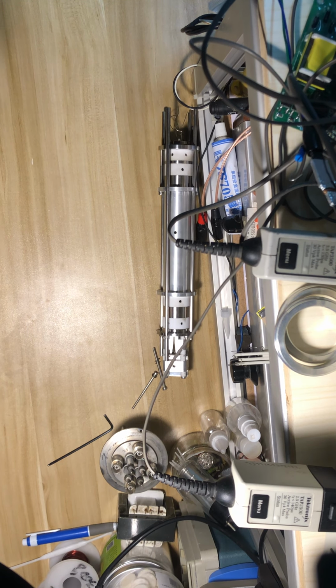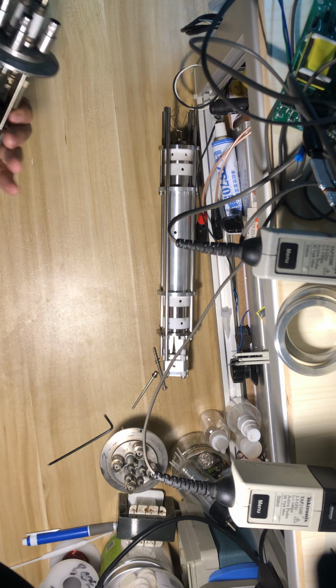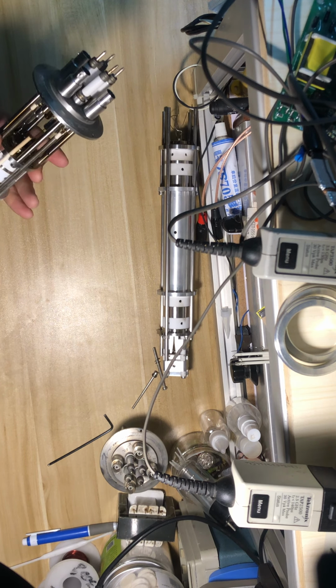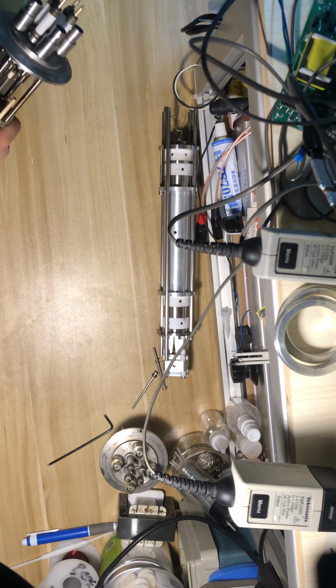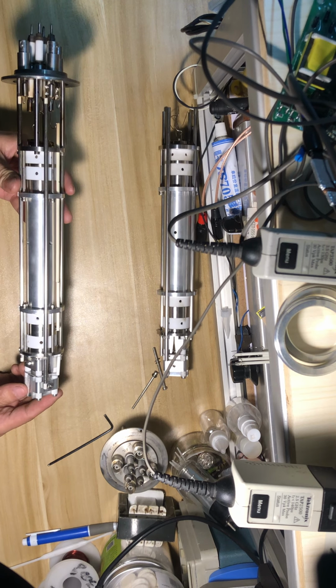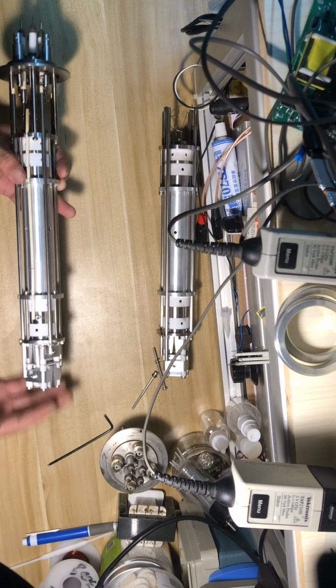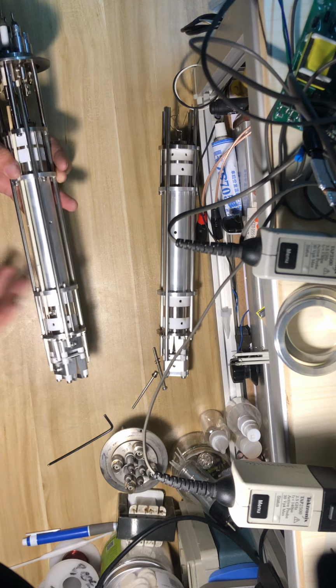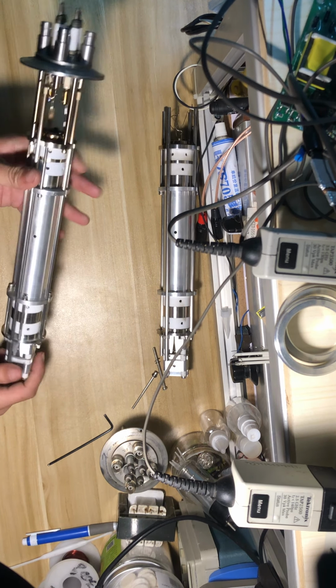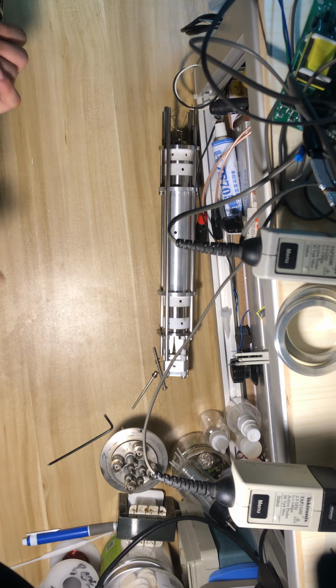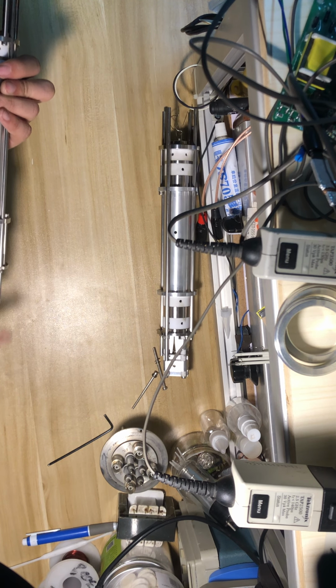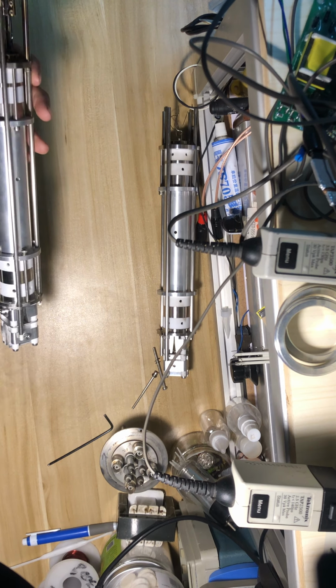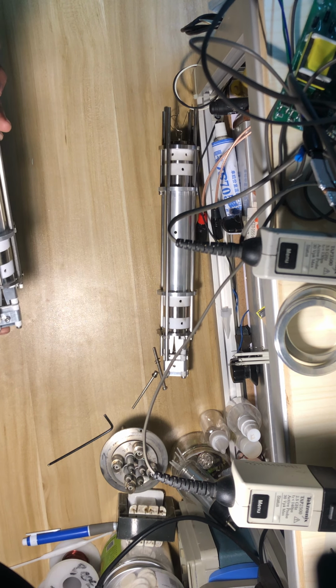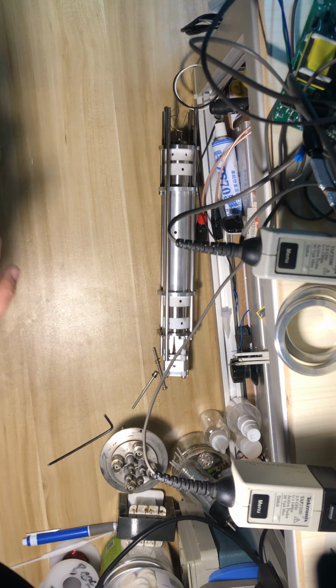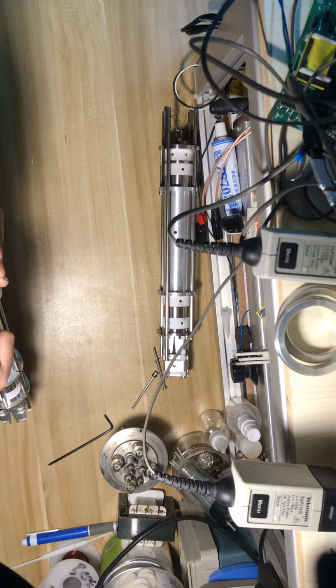This 4 BNC connector is actually used for the electron deflection electrode. So this is a pretty old design of an electron gun. In normal operation, it's basically like an old CRT, or maybe you have seen this in a pretty old oscilloscope. It's the same, but it's much bigger. It's using an electrical field to make the electron beam deflect, so it can produce a scan pattern, so it can be used to scan the sample. In the middle of this, we can see the filament or the cathode.